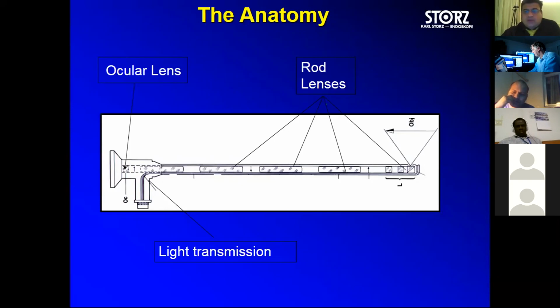Okay, so whenever light is transmitting from one medium to another medium, there is always a light transmission loss. And we say in our product there's very minimal loss, because we put a very high quality refractive index coating on these rigid rod lenses. Between the rod lenses, we put what are called metal spacers, so that if there is a mechanical thrust, it accidentally hits the sterile trolley or falls a little, the endoscope is protected.